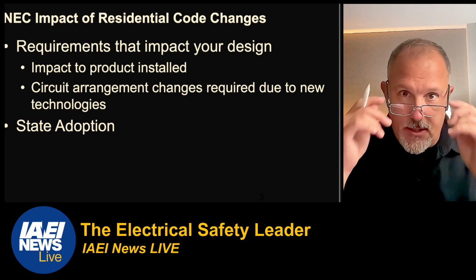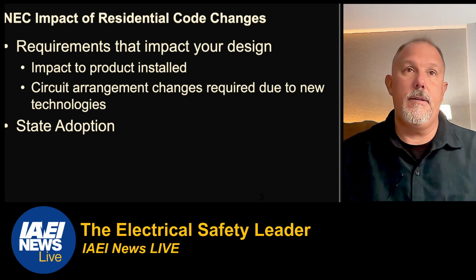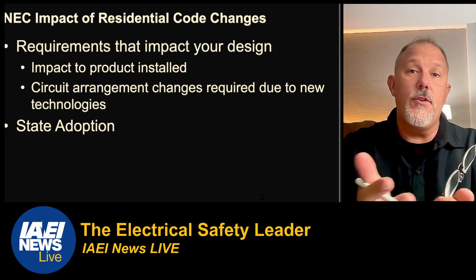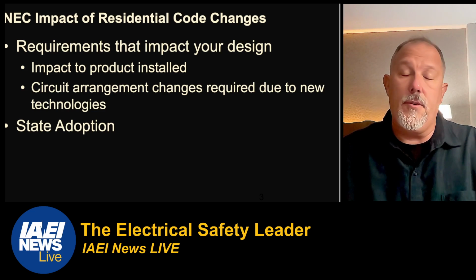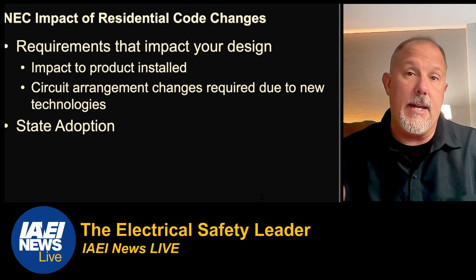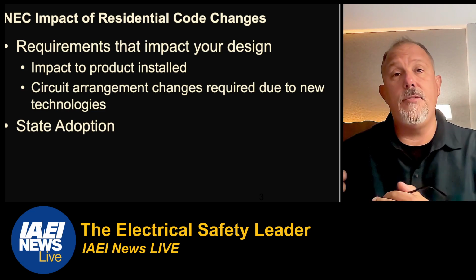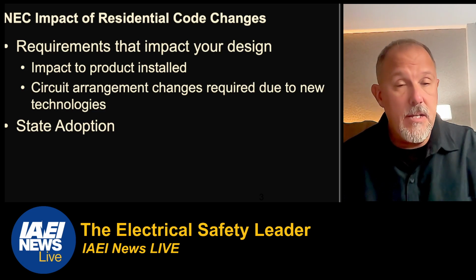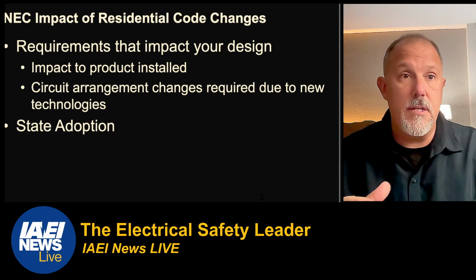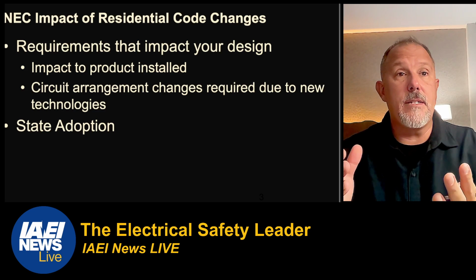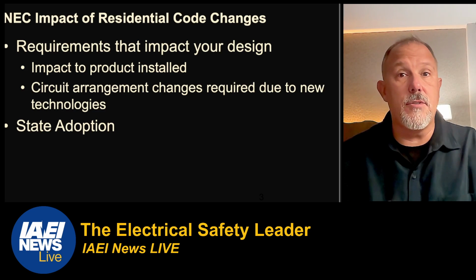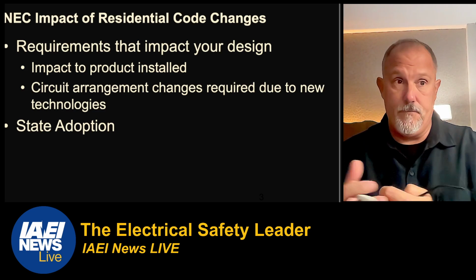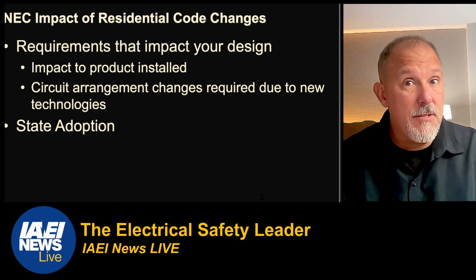So be mindful that all of that makes a difference, especially if you have a new room that requires AFCI, or you have a new area that requires GFCI. You may want to adjust how you design and lay out your system to minimize impact in case there's a trip on that circuit. Minimize leakage currents in your applications.